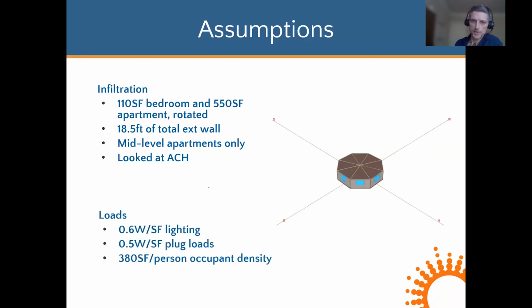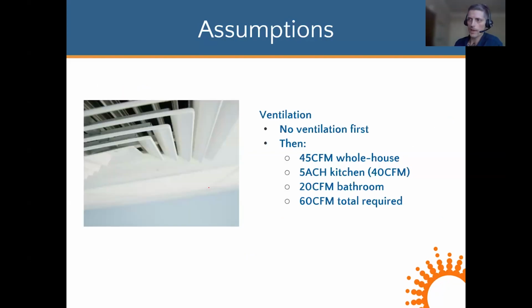We applied some loads to the space: lighting, plugs, and occupants. And for ventilation, we looked at a scenario with no ventilation first as a baseline to see the air quality and energy consumption. Then we applied ASHRAE 62.2 2016 values for whole house ventilation and exhaust requirements, kitchen and bathroom, landing on a total of 60 CFM, with the exhaust requirement being the dominant flow.